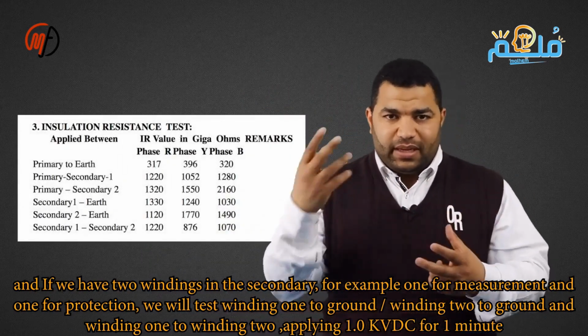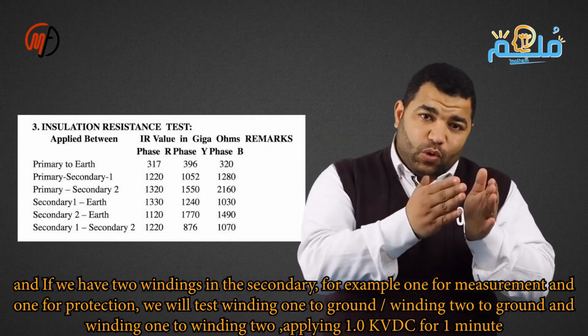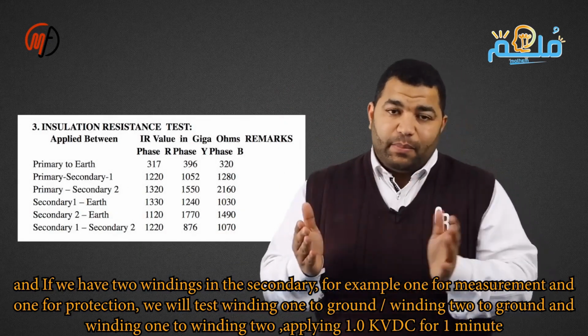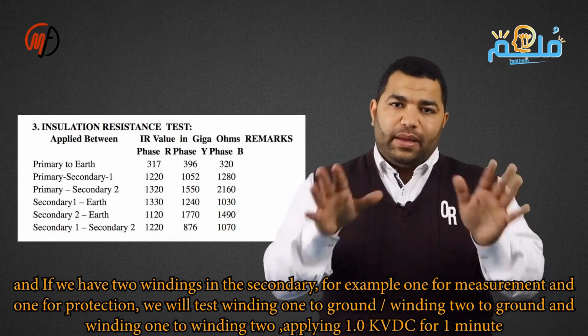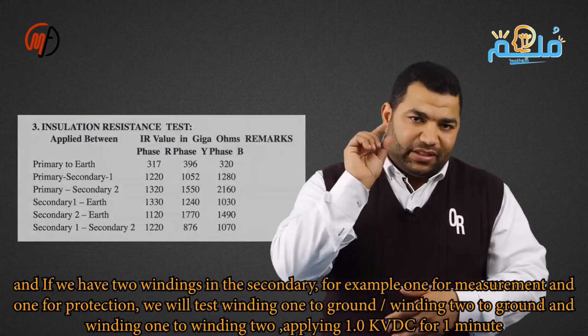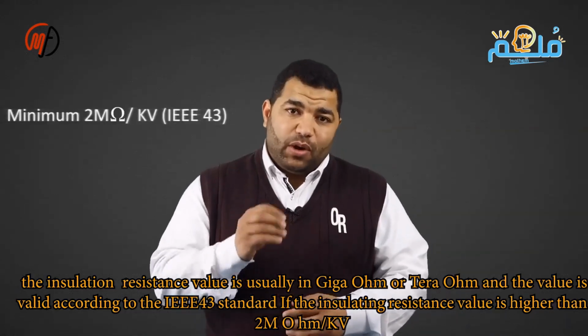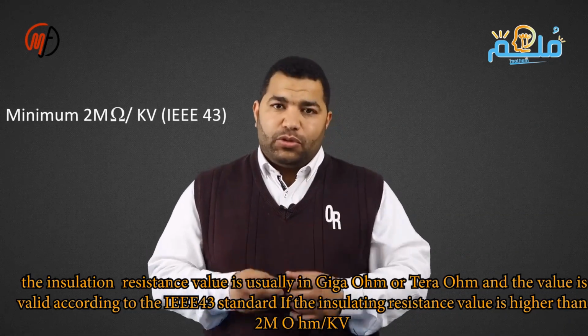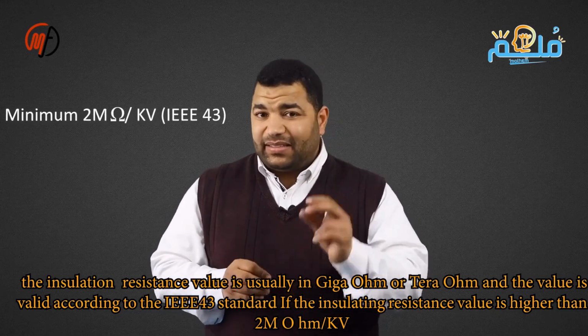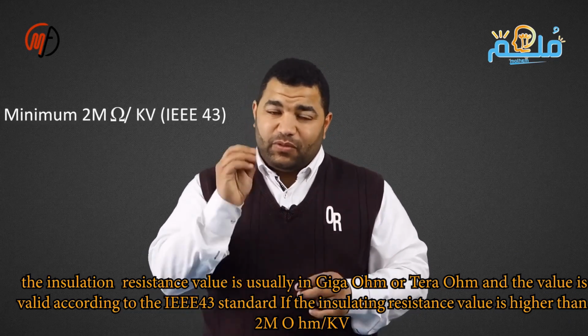One is for metering and the other for protection, for example. We test each winding by applying 1 kV DC for 1 minute. Typically, the insulation resistance value should be in giga ohms or tera ohms, and according to IEEE 43, the value is considered acceptable if the insulation resistance is above 2 mega ohms.